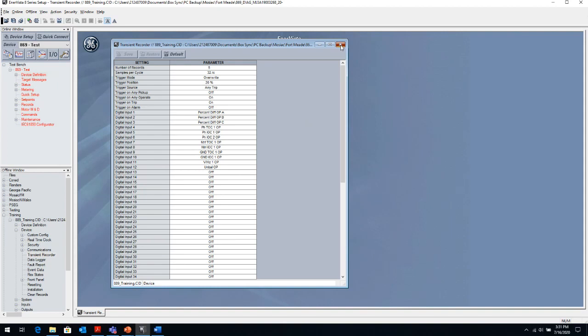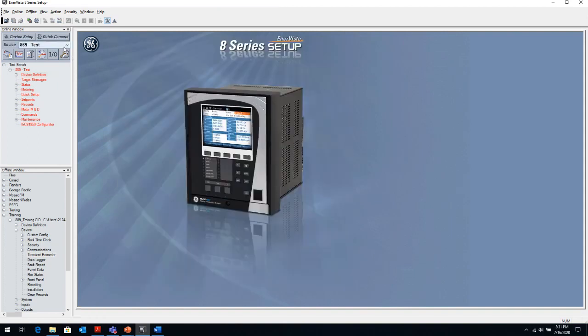Now, one icon I want to mention, this icon on the top right here, it's called the service report. So the service report is very important if you want us to look at something that's happening in your power system or in your relay. You have a disturbance, and the relay might have tripped, and you didn't expect it to trip, or it did trip, but not on what you expected. So what we would normally ask you to do is send us the service report.